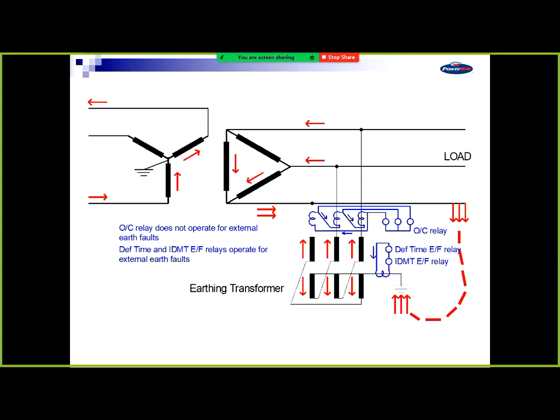If you've got an external earth fault outside the transformer zone, you get earth fault current flowing in your earthing transformer, up the neutral, through each of those windings. You get 2 units going back, so that's all zero sequence current, and it's I0 in each phase. So you get 2 lots flowing back into the transformer, coming out on the faulted phase, plus the single one coming up from that phase on the earthing transformer, and you get 3 lots of I0 current flowing out. So your total earth fault current is equal to 3 times I0. That's where your 3 lots of I0 come from.